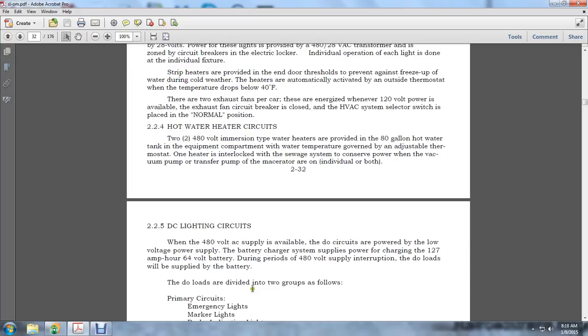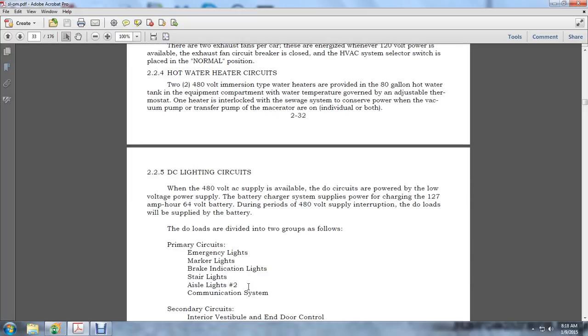225, DC lighting. When the 480-volt AC supply is available, the circuits are powered by the low voltage power supply. The battery charger supplies power for charging a 127 amp hour 64 volt battery. During periods of 480-volt supply interruption, the DC loads will be supplied by the battery.